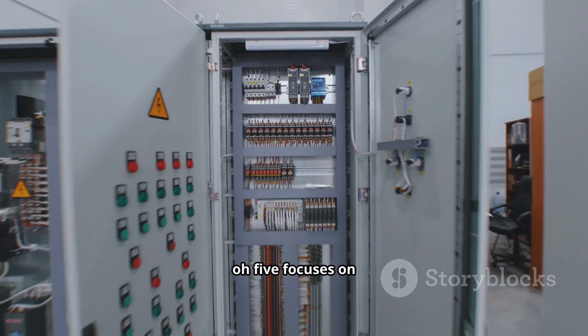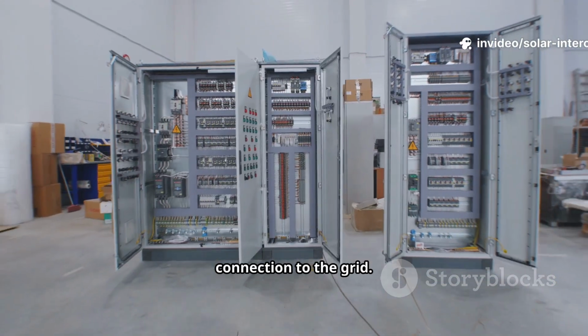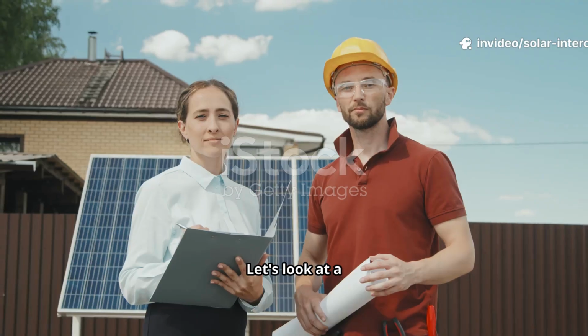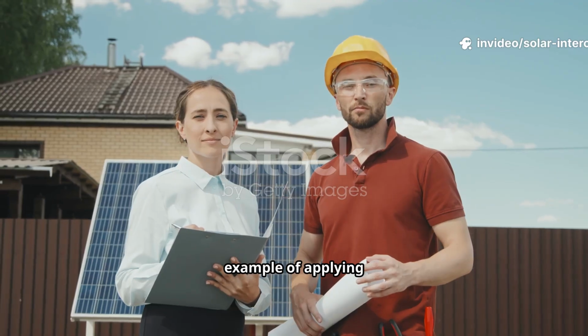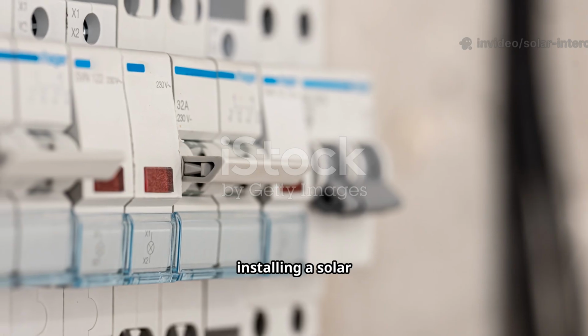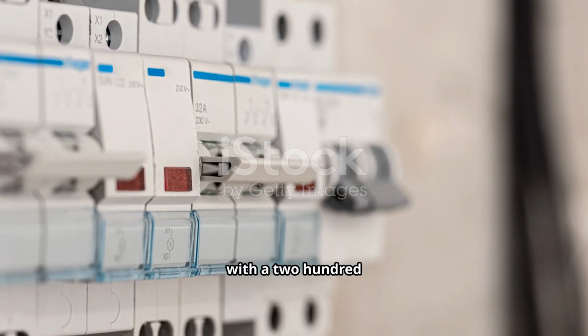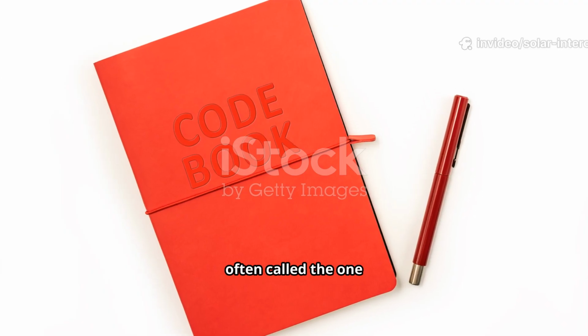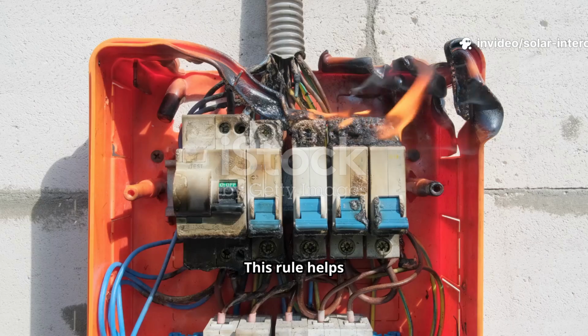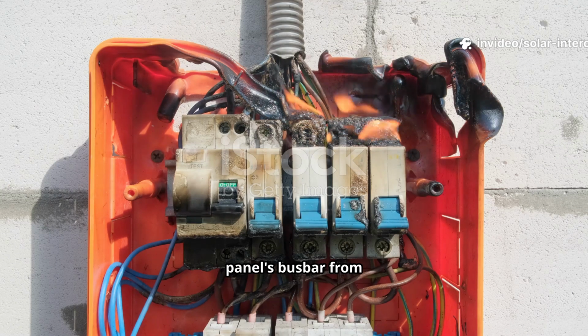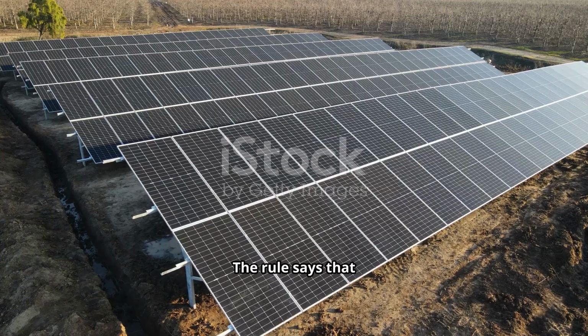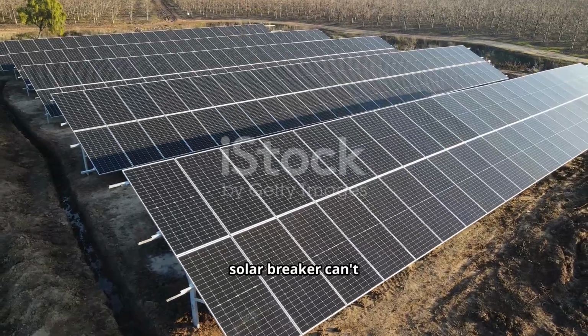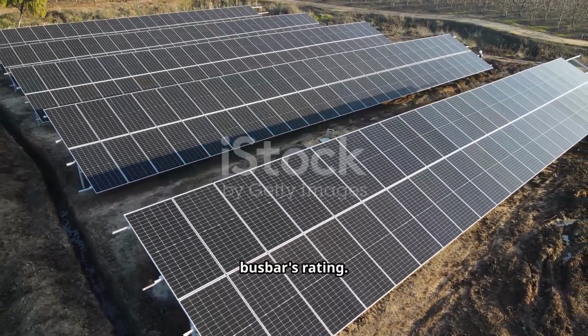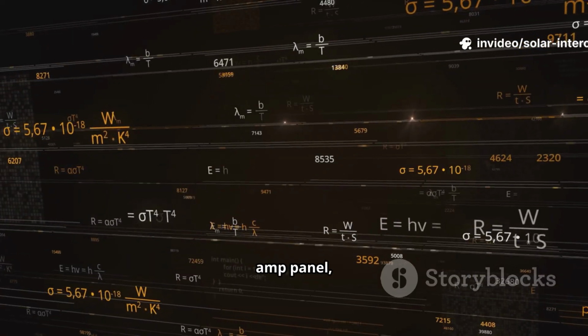NEC Article 705 focuses on the point of connection to the grid. This is the interconnection part. Let's look at a common real-world example of applying NEC rules. Imagine you're installing a solar system on a house with a 200-amp main electrical panel. NEC Article 705 has a rule often called the 120% rule. This rule helps prevent the main panel's bus bar from being overloaded. The rule says that the sum of the main breaker and the solar breaker can't be more than 120% of the bus bar's rating. So for a 200-amp panel, 120% is 240 amps.